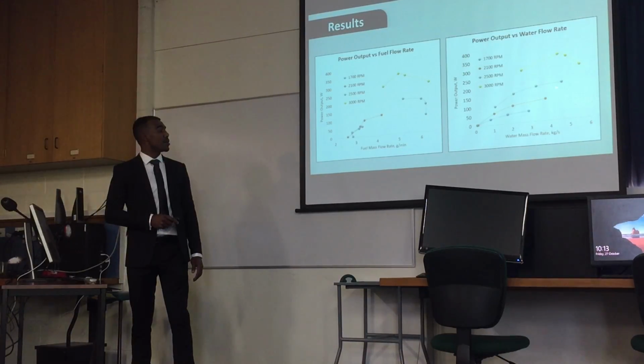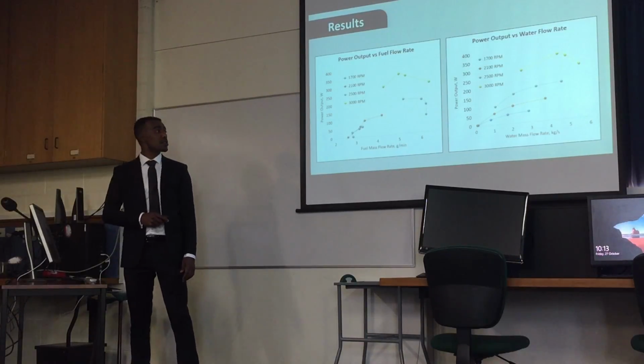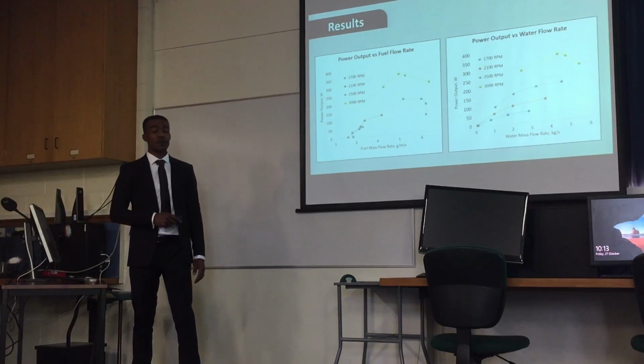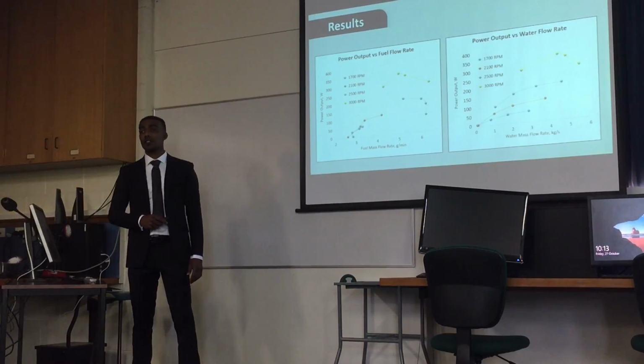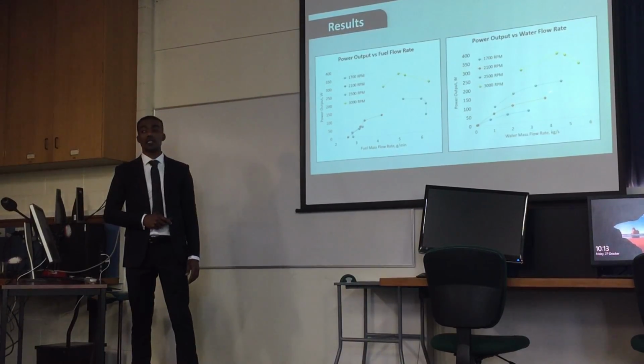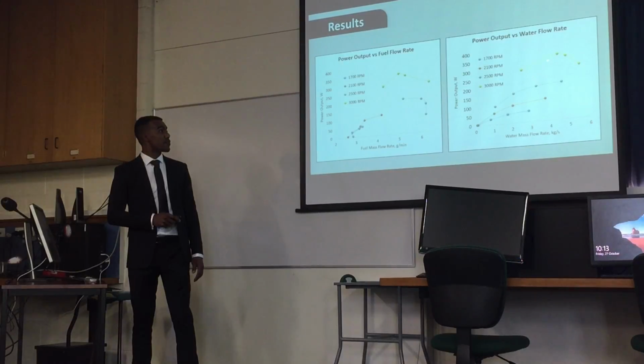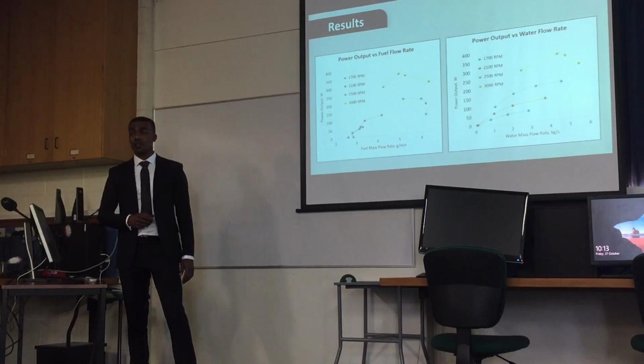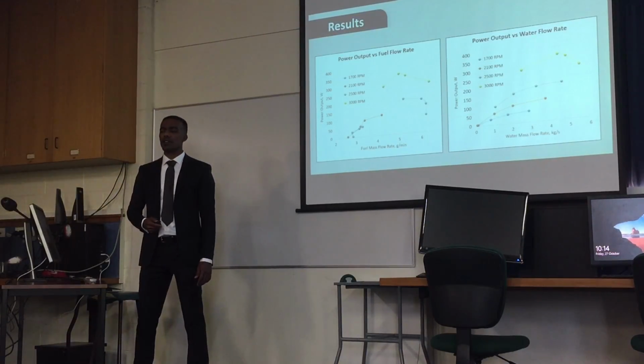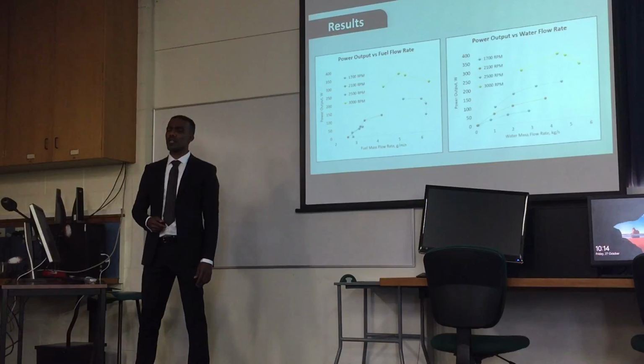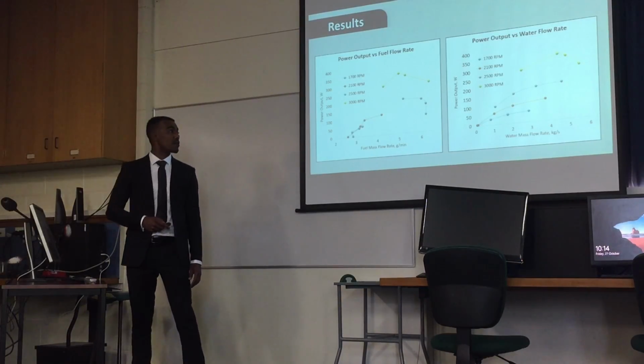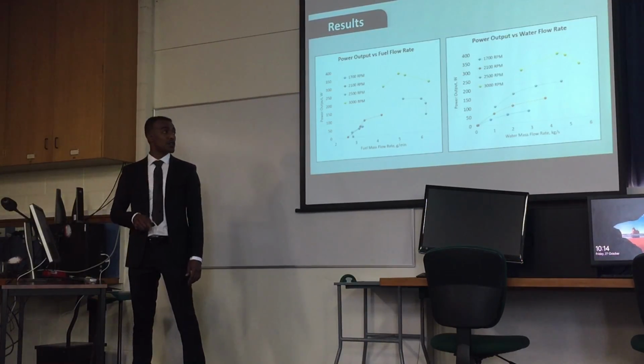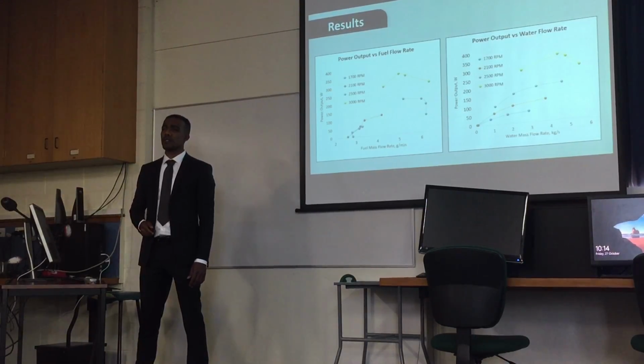I also looked at the water flow rate and the power output against that. You see the 1700 to 2500 looks very similar, looks like a pump power curve, but that's actually not for the pump, that's for the system. For the 3000 RPM, that's different, and that's because the power is not dependent only on the water flow rate, but also depends on the pressure in the system. So closing the valve, changing the pressure, reduces the water flow rate, however, increases the pressure in the system.